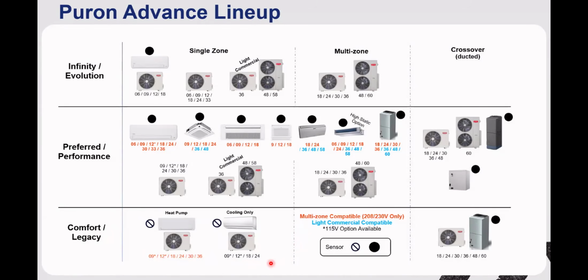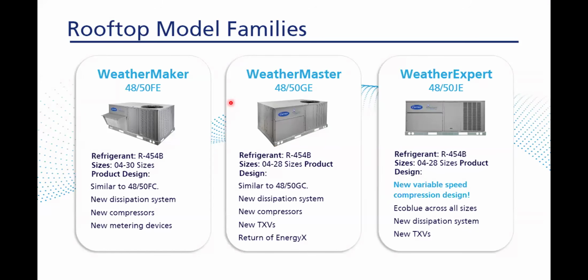So let's just for argument's sake say, hey, if it's less than 4 pounds, you don't have to have a leak sensor. So a window unit, no leak sensor. A PTAC in a hotel, you don't need a leak sensor, right? And in some cases, these ductless mini splits, if they're relatively small coils, they don't have a lot of refrigerant volume. And if they tell you, hey, keep the piping length less than XYZ, they can thereby say you don't need a refrigerant leak sensor. You could still buy one if you want and plug it into the board, right? If you want to, or if your piping is so long that it needs to, but you don't necessarily get it automatically like you do on the higher end stuff.